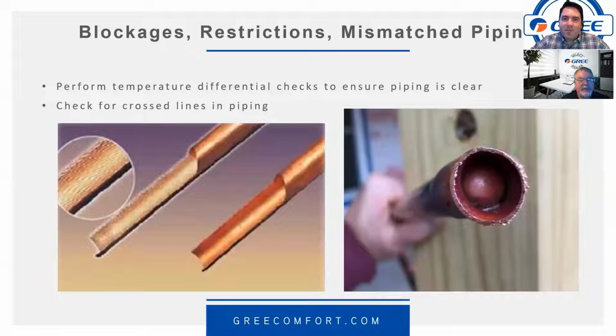So, troubleshooting test points, blockages, restrictions, mismatched piping. This is an actual picture that we just came across. A friend in upstate New York sent that to me. That's the bonnet from the flare nut that was left on and pushed its way out into the pipe. Yep. Well, I'm sure that wasn't any of the people on this call, but just in case, if you've never seen that. And I've seen plastic, sometimes a pipe will have a plastic insert in there. I've seen those in there as well, and all kinds of mayhem. But just make sure that the piping is clear. You can perform a temperature differential check to ensure piping is clear, and check for cross lines in piping.